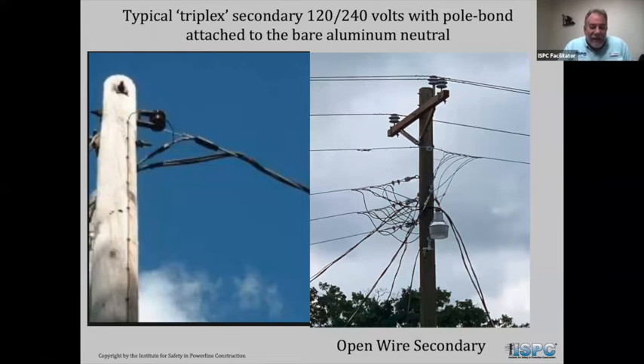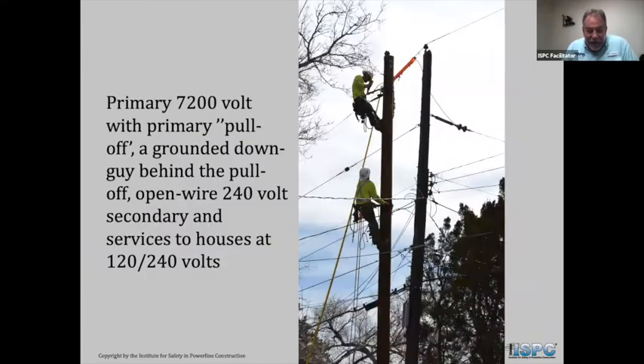Okay. We don't have a lot of time now, but you can see on the right-hand side, that's that same picture I showed earlier. You can see how the system neutral is tied to all of those neutrals, and then you have one wire that's going back to a transformer from there. A lot of your typical single phase is about 7,200 volts, 7,600 volts in some companies. It just depends on what the company is using.